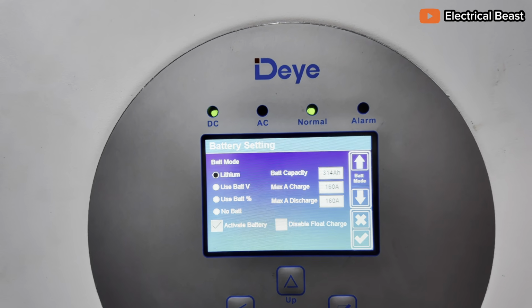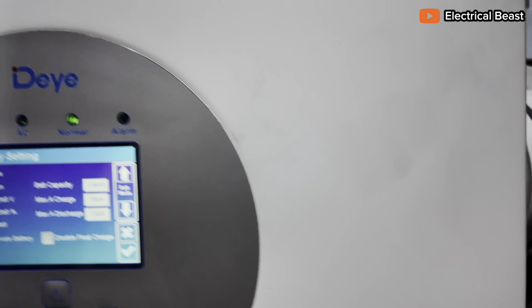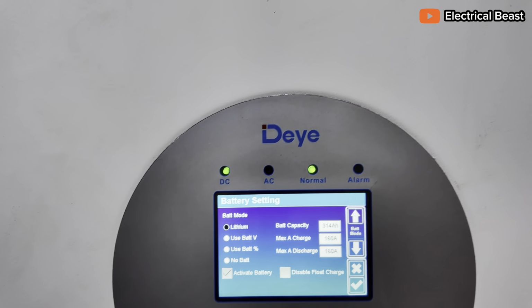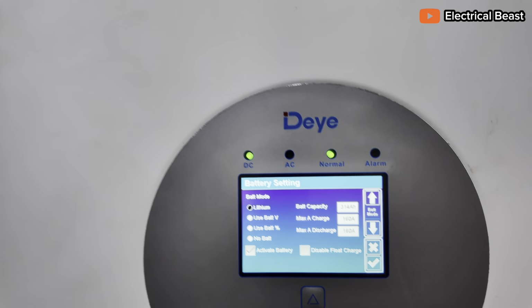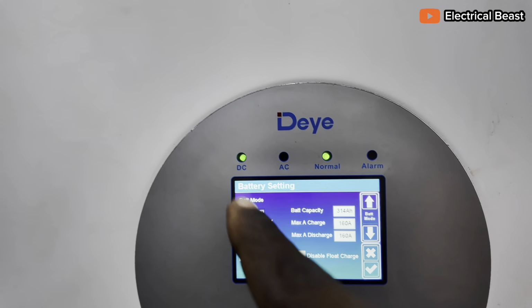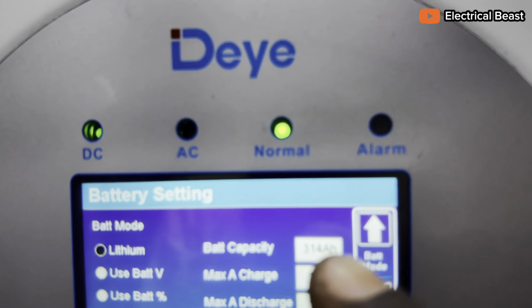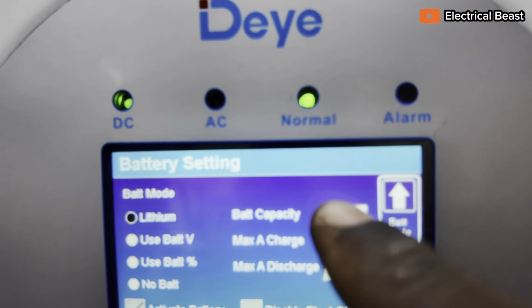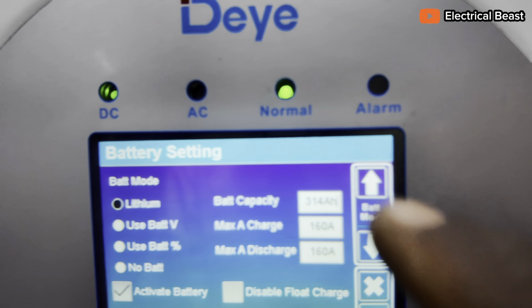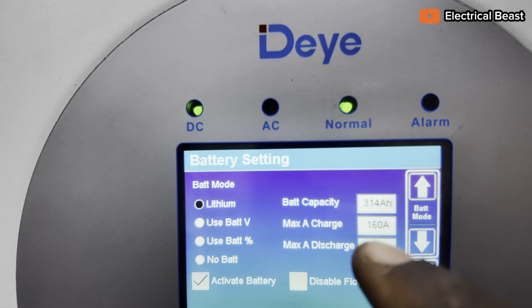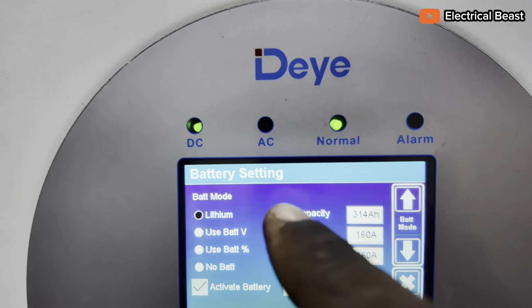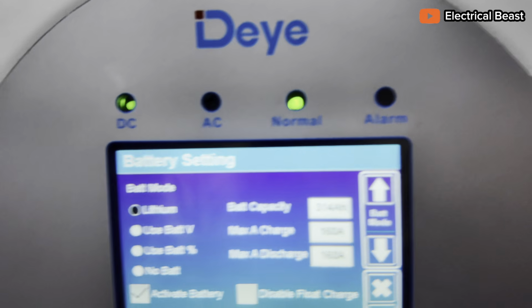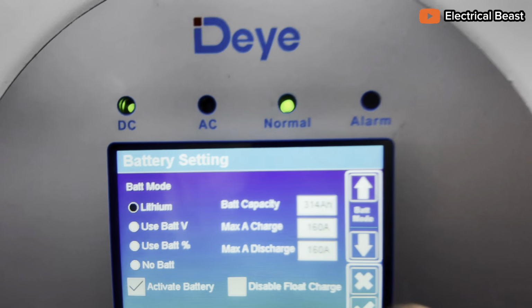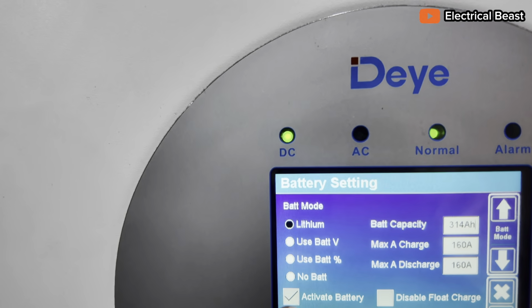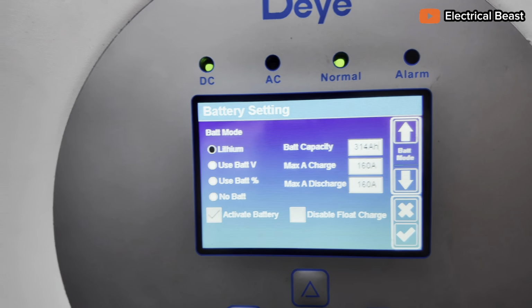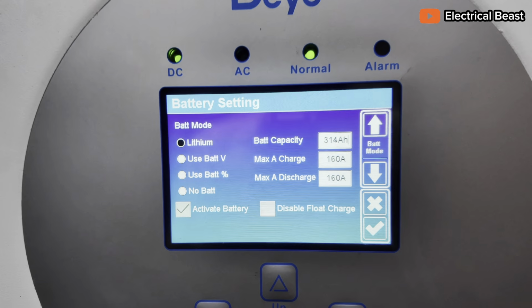When you turn on the inverter, it doesn't supply until you tap on the particular battery type you're using. If you're using a lithium battery, tap on lithium, then set the capacity yourself, it's editable, just tap with your finger and use the up or down button. We already set the battery capacity to 314 ampere hours, 160 amps. Then tap activate battery, and the battery activates.